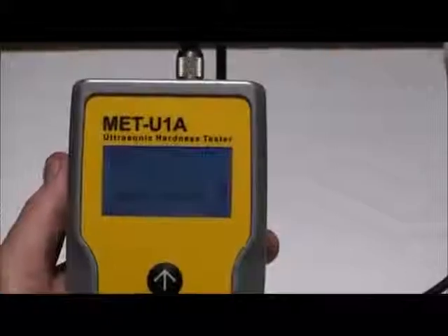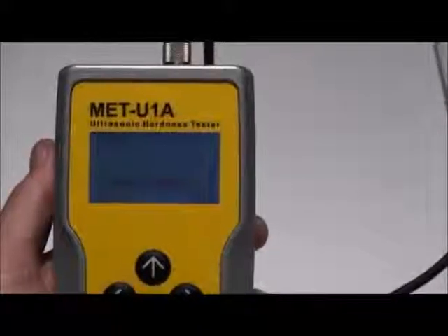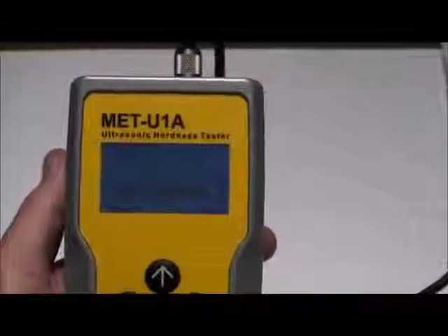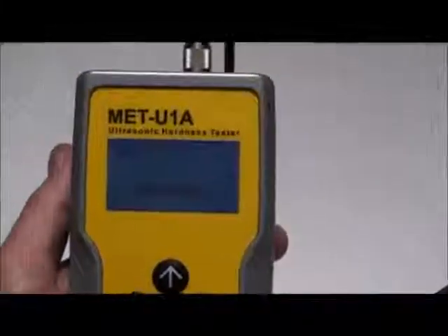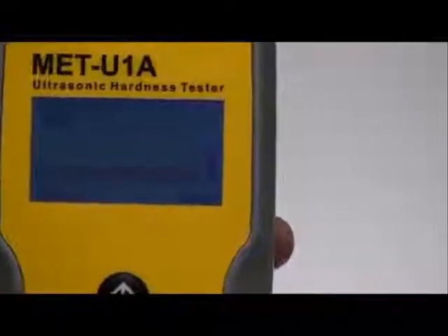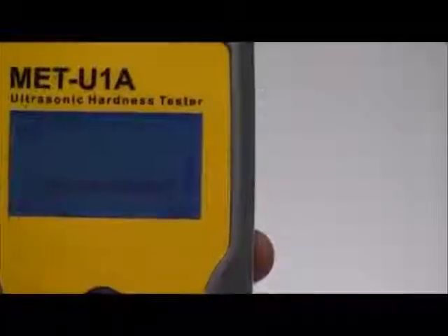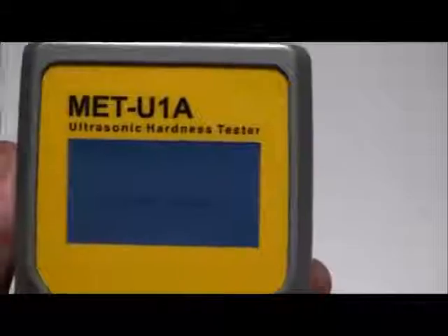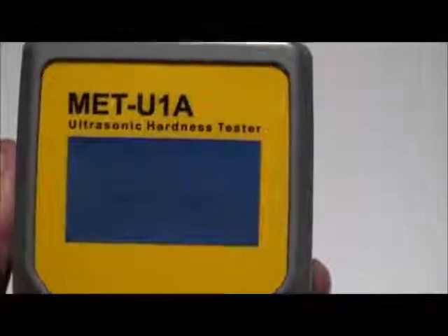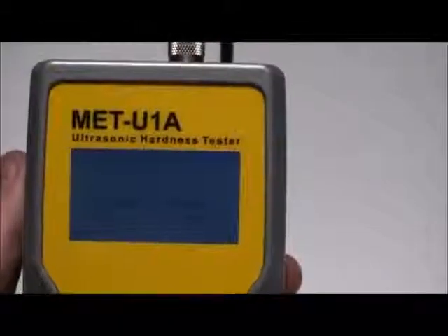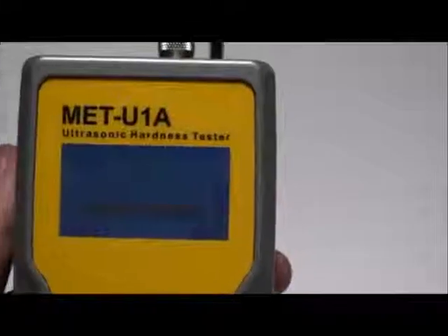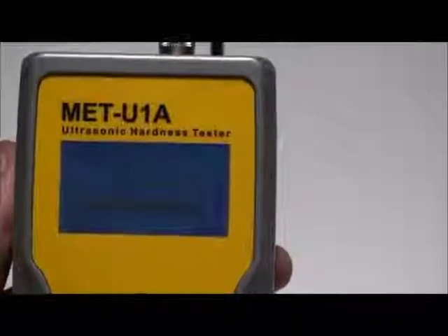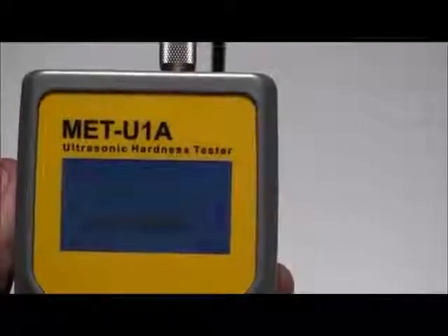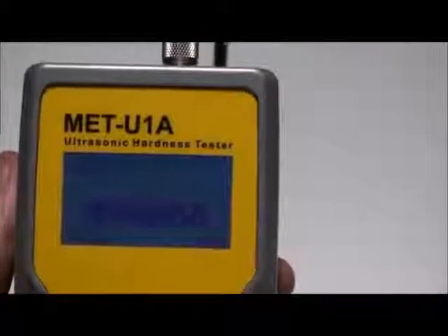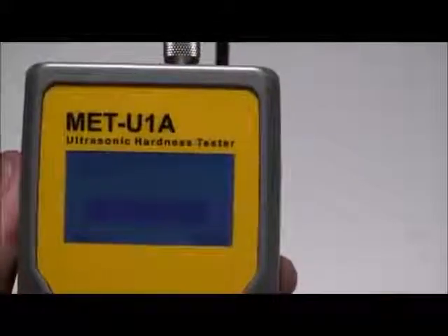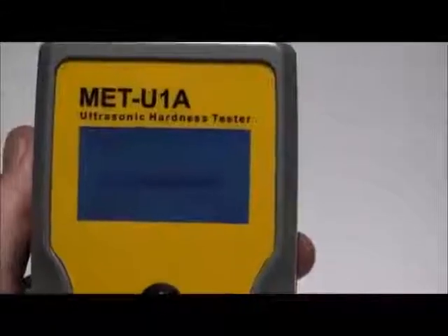Once clicking the down arrow to select your scale, you will now see the test blinking with arrows. This is the center point of the menu system. Scroll right using the right arrow, and then you will see calibration blinking. A down arrow button will take you to the calibration mode. However, note it is dangerous to do so in an already programmed scale, unless you have test blocks for that scale in the correct material. Pressing the right arrow button while calibration is blinking will bring you to process. If you hit the down arrow button, you can see it will take you to calculate mean value, or if pressing right or left, clear archives.